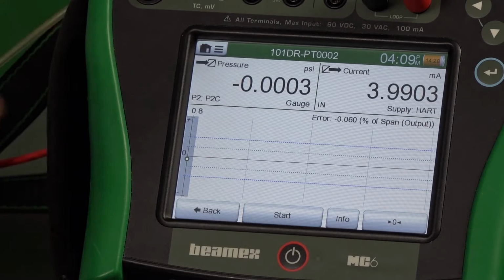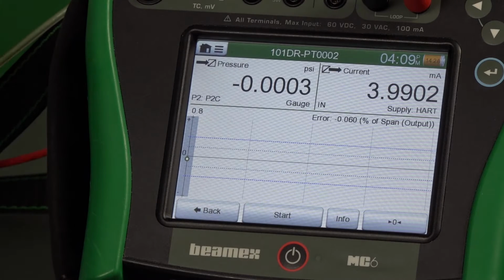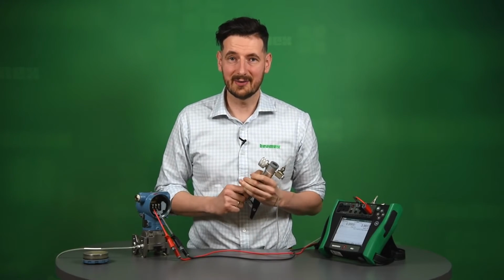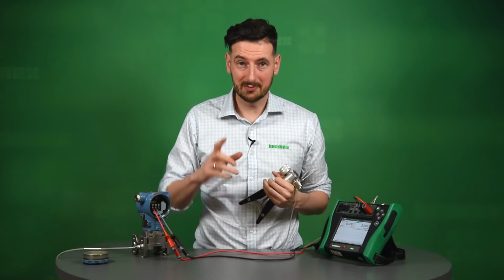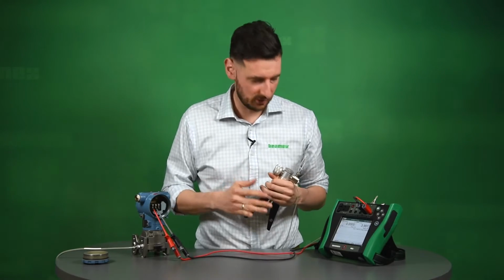You can see right now we vented off the system. We read more or less 4 milliamps, and I think we're ready to go. Okay, we're ready to start our calibration. So we're going to document those 5 going up and 5 coming down.